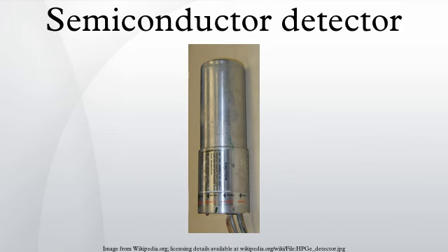The major drawback of germanium detectors is that they must be cooled to liquid nitrogen temperatures to produce spectroscopic data. At higher temperatures, the electrons can easily cross the band gap in the crystal and reach the conduction band, where they are free to respond to the electric field, producing too much electrical noise to be useful as a spectrometer. Cooling to liquid nitrogen temperature reduces thermal excitations of valence electrons so that only a gamma ray interaction can give an electron the energy necessary to cross the band gap and reach the conduction band.